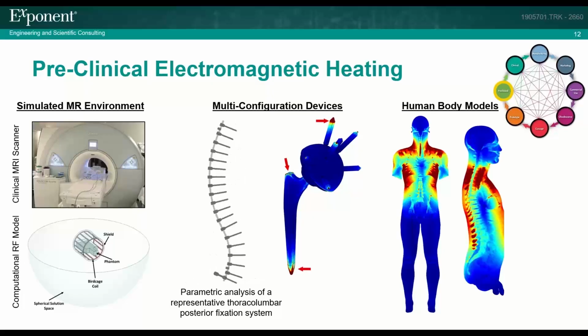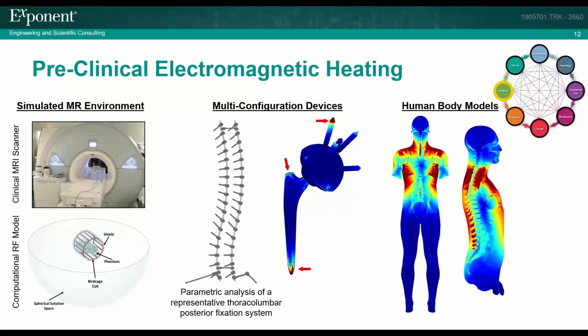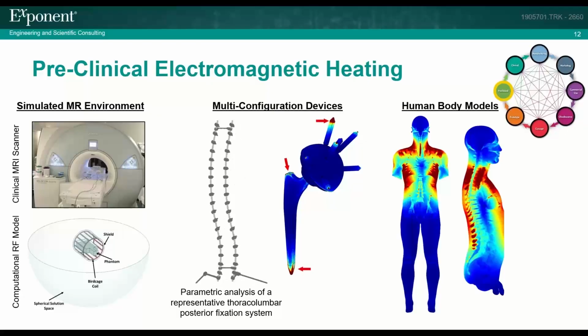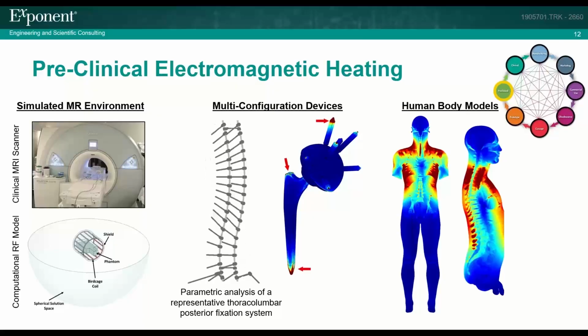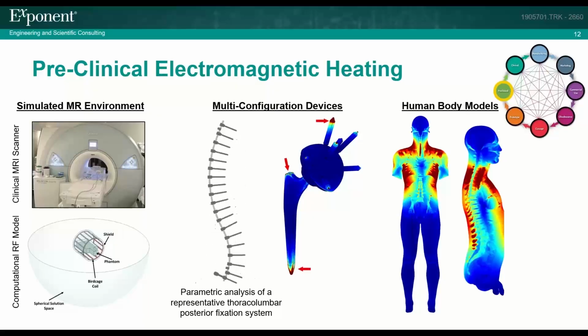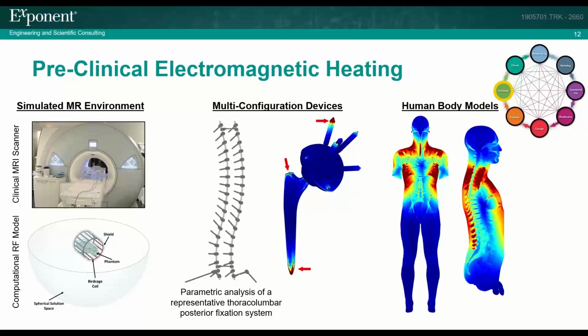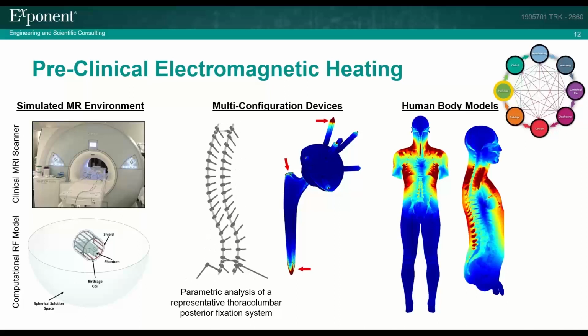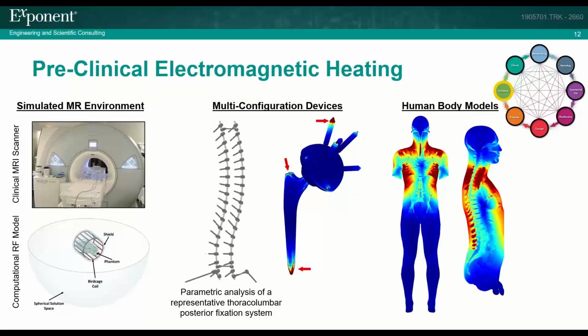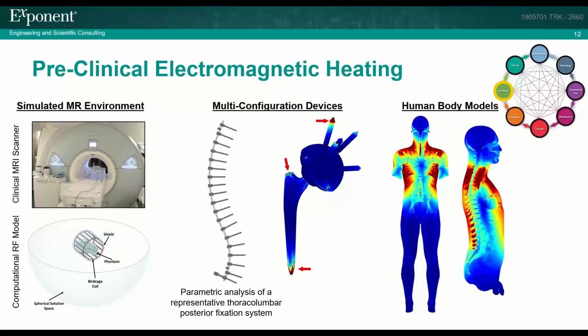Finally, for this phase, I'd like to allude, like I alluded to in the panel discussion earlier, and which was gone into in much greater depth in David's talk right afterwards, to the preclinical evaluation of MRI compatibility for both passive and active implantable medical devices, which is of increasingly significant interest to medical device companies and regulators alike. While there are a number of risks that must be accounted for regarding the interaction between the device, the electromagnetic field, and the body, one of the most complicated of those risks is that of radiofrequency-induced heating. With a properly validated and verified simulation framework, we can perform comparative or even predictive studies of RF-induced heating.